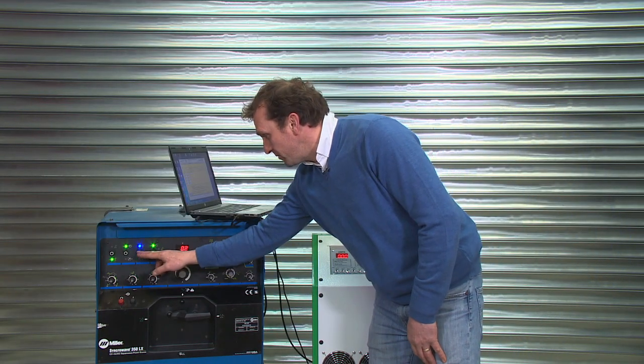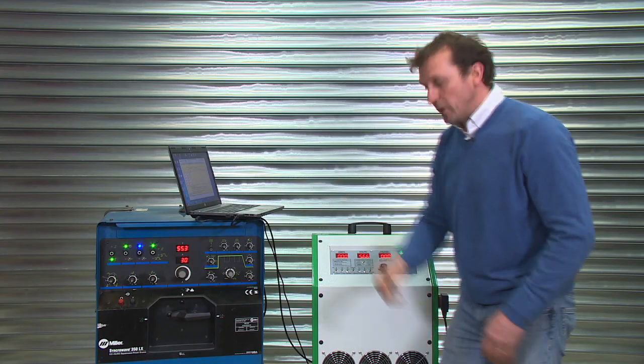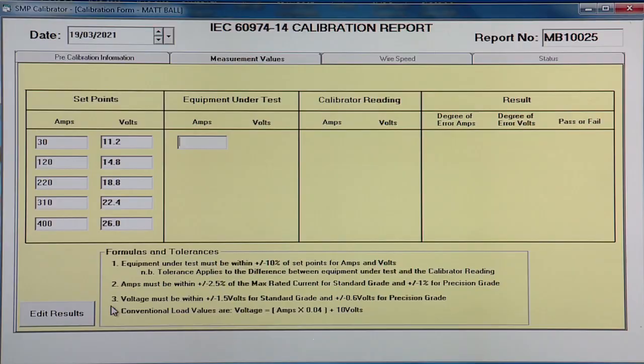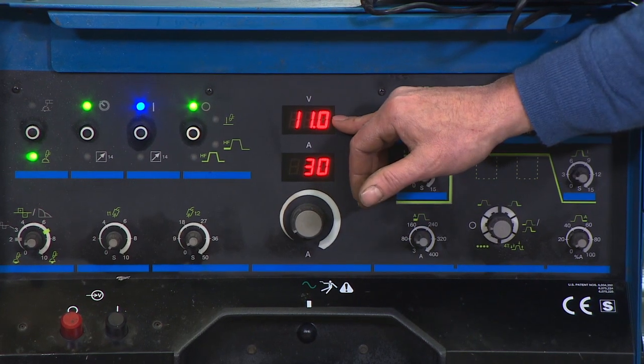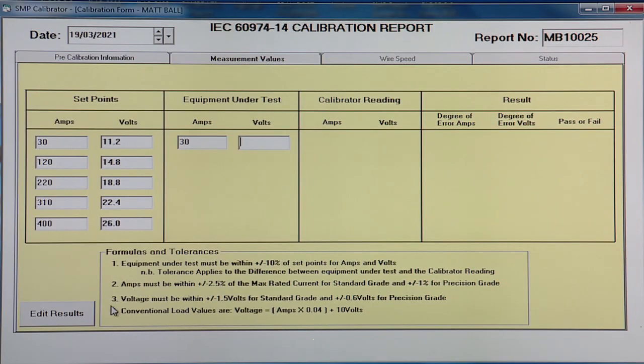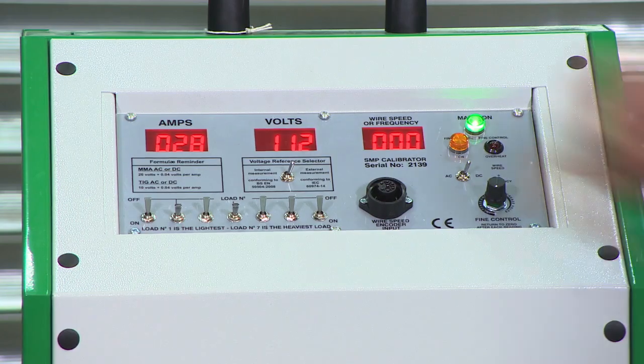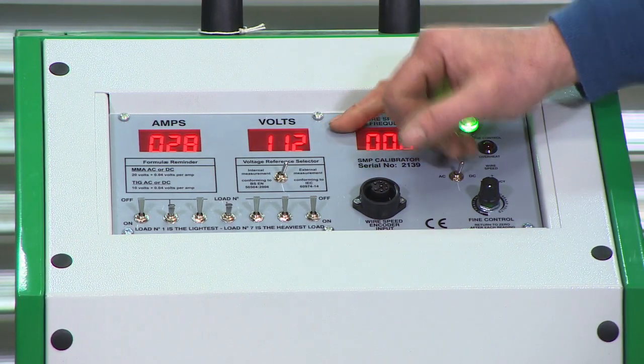So now we're basically going to repeat what we've done, but in the opposite polarity. Again, we energize the machine, either on the panel or by the trigger. And then back through the process once more. So we're looking for 30 amps, 11.2. We record 30 amps, 11.0. And then the calibrator reading of 28 amps, 11.2.